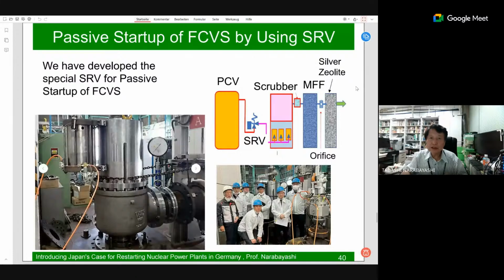And also the passive startup of the filter containment system was developed by using a safety relief valve. We asked valve firms to develop a very low pressure safety relief valve. The main steam line SRV works under a pressure of 7 or 8 megapascal, but this SRV works below 1 megapascal, and we tried to develop it, and we succeeded.